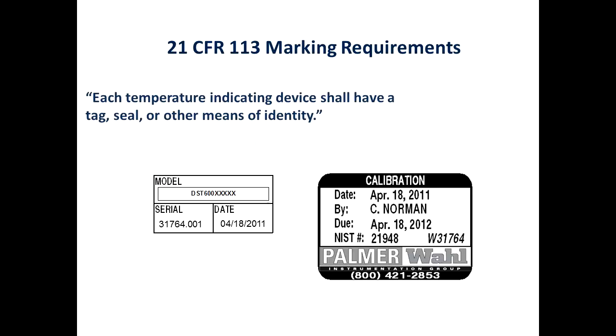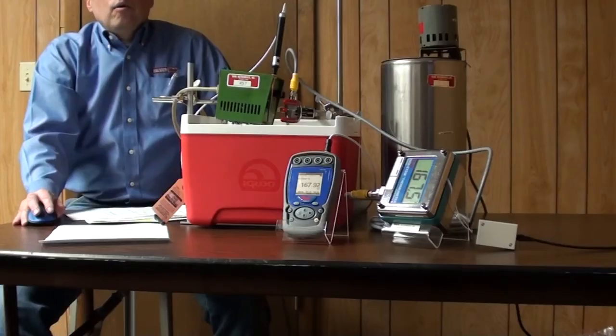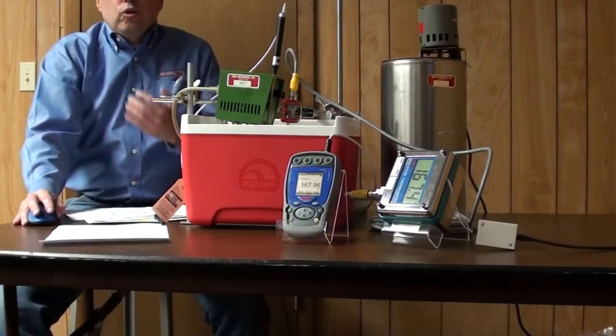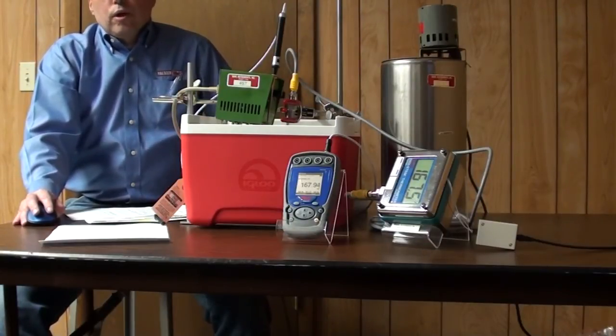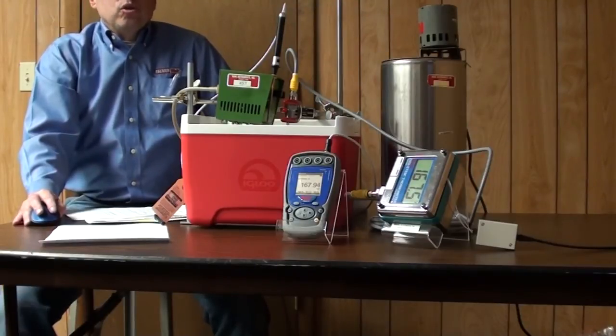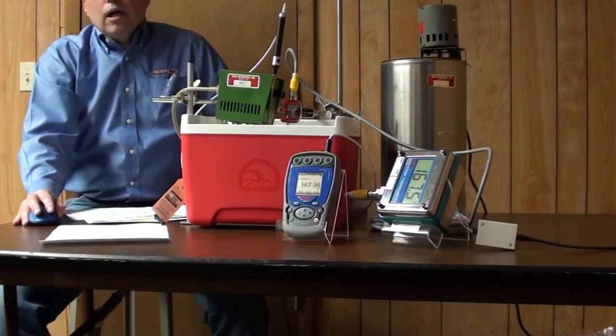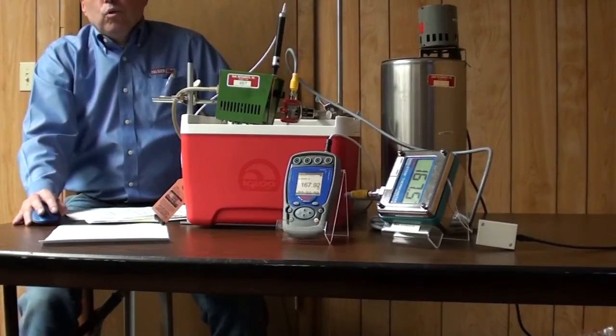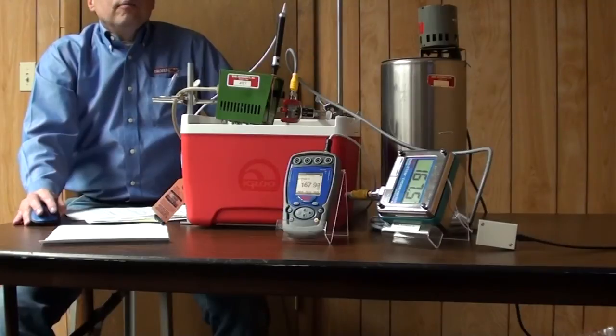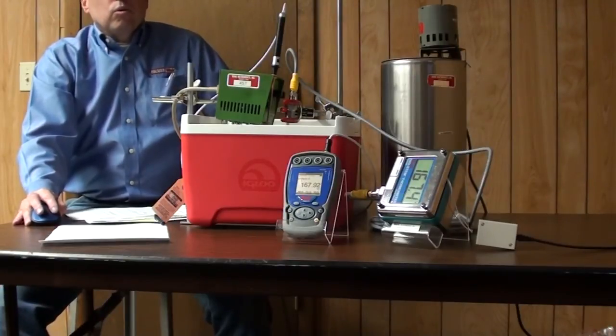Date it was calibrated, the technician that calibrated it, and the due date, which in this case was a 1-year calibration interval. There's the NIST number, so we can trace all that information back from that number. And then one other thing we add, because this is a unit that came back to us, is our order number. In this case, this was a new unit, and the order number matches our serial number, you can see. But if you were to return that a year later, this number would have incremented by then, so it wouldn't match any longer at that point. But that is not part of the requirement to have that order number there.